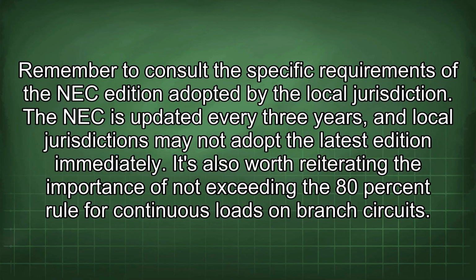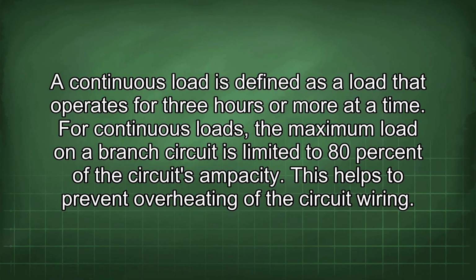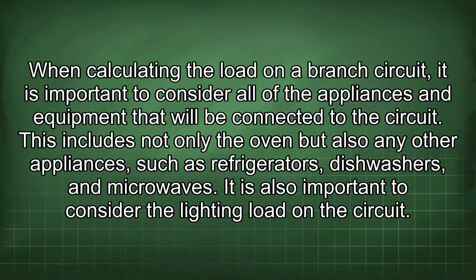It's also worth reiterating the importance of not exceeding the 80% rule for continuous loads on branch circuits. A continuous load is defined as a load that operates for 3 hours or more at a time. For continuous loads, the maximum load on a branch circuit is limited to 80% of the circuit's ampacity. This helps to prevent overheating of the circuit wiring. When calculating the load on a branch circuit, it is important to consider all of the appliances and equipment that will be connected to the circuit.